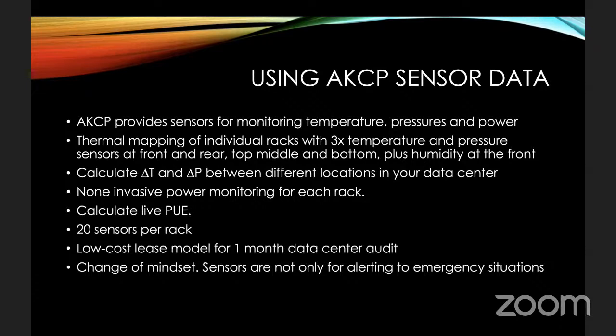Now, you go to most data center administrators and say that you want a budget to put 20 sensors per rack. They're probably going to laugh at you. You're never going to get approved that budget, right? Which is why we are proposing a low-cost lease model for a 1-month data center audit. You get 20 sensors per rack. It's completely wireless. It doesn't touch their network. It's the ultimate in security. There's no need to hook it up to their network at all.